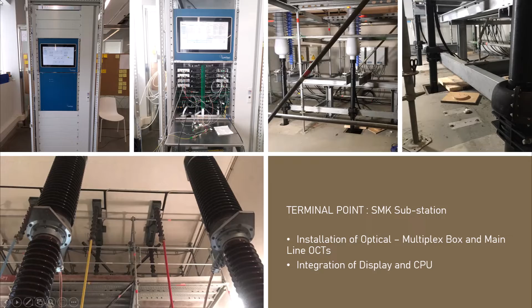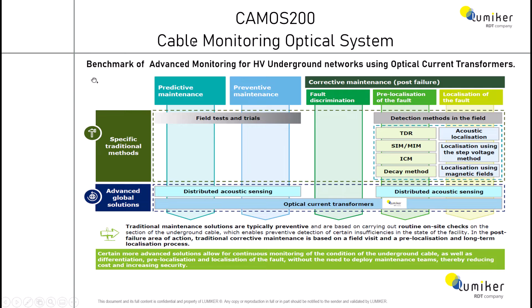The implementation of optical solutions will generate efficiencies that consumers may benefit from, bringing down the system cost of energy. CAMOS is the only current system able to monitor the real current flowing through the cable screens, including sheath ground circuits, to analyze the insulation health in the cable.